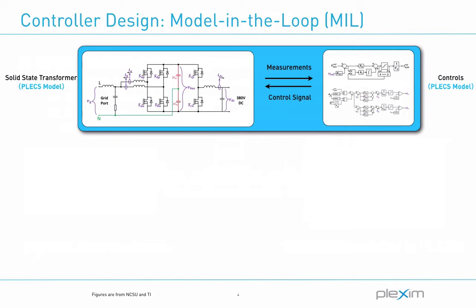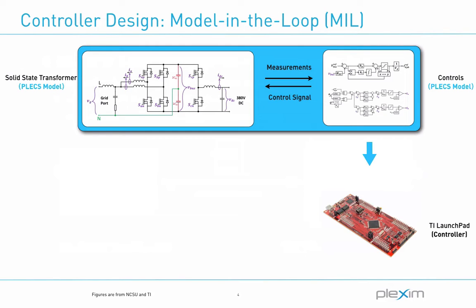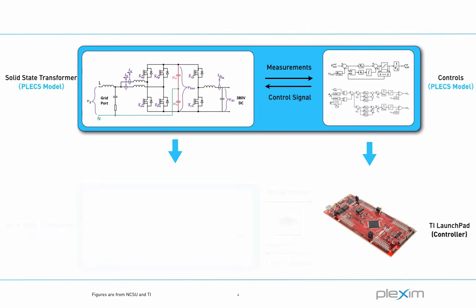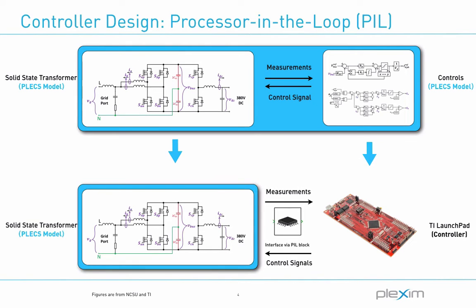Assuming you are using a digital-based control system, further along in your design cycle you will likely need to either automatically generate or hand-code the controller code onto an actual microcontroller in order to test its performance. Before connecting that to a physical power stage, such as an SST, and risking component damage, however, you have an option to test that compiled C code on the target, along with the virtual environment of a power stage model in PLECS, which you likely already have from the previous step.